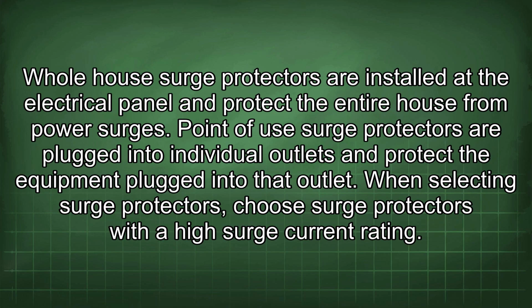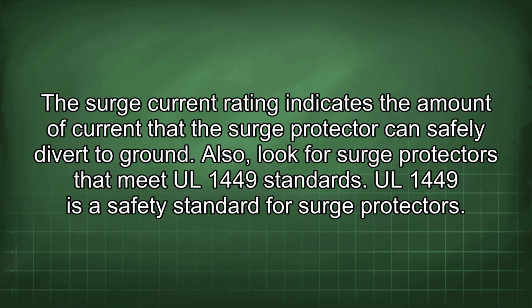When selecting surge protectors, choose surge protectors with a high surge current rating. The surge current rating indicates the amount of current that the surge protector can safely divert to ground. Also, look for surge protectors that meet UL 1449 standards. UL 1449 is a safety standard for surge protectors.